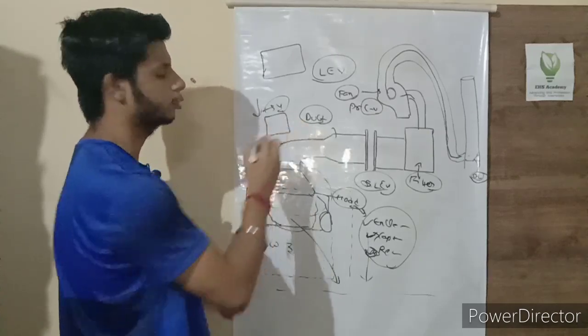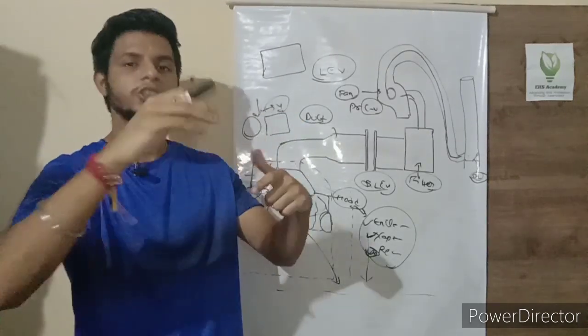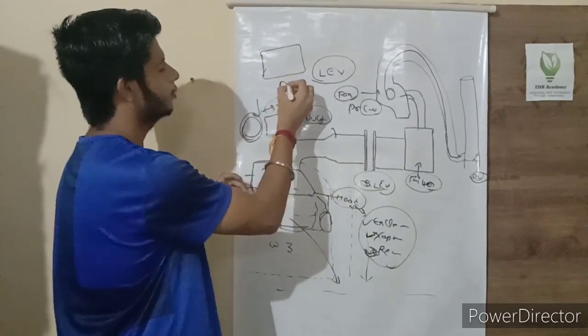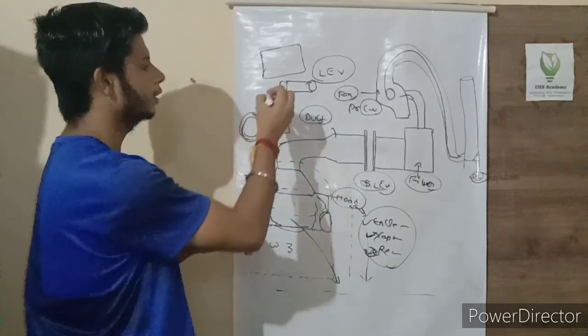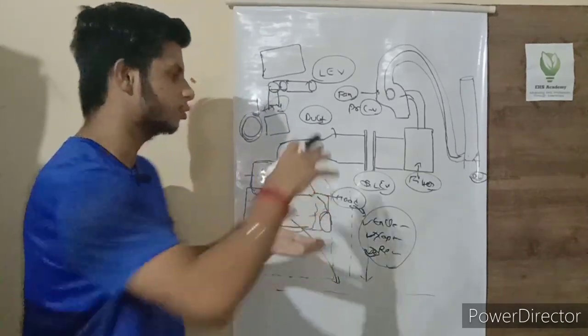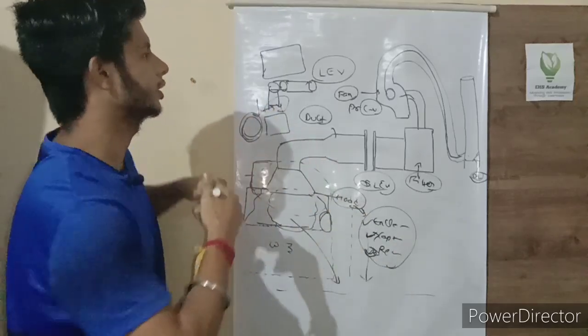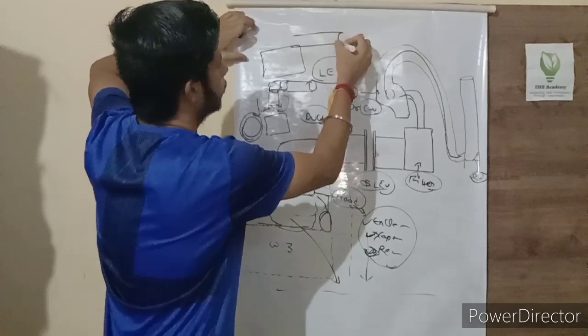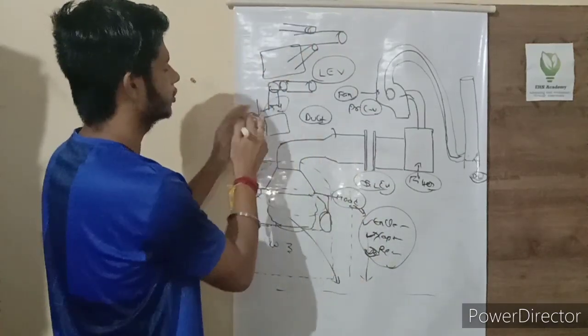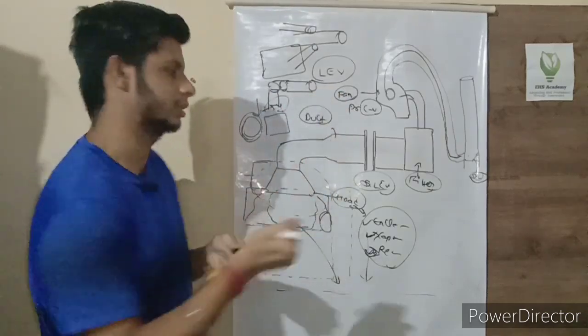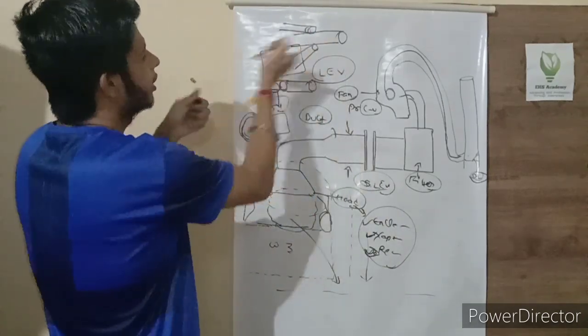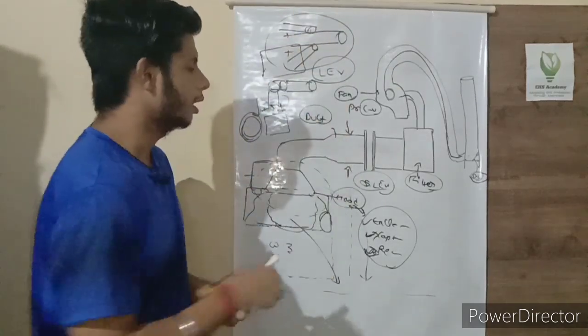For ducting, generally round ducting is preferred over square ducting. One important issue is turbulence. If you have sharp bends in the ducting, turbulence causes the ducting to shake, which can damage it. To avoid turbulence, when joining two duct sections, use gradual curved bends instead of sharp bends, so airflow transitions smoothly and turbulence is minimized.